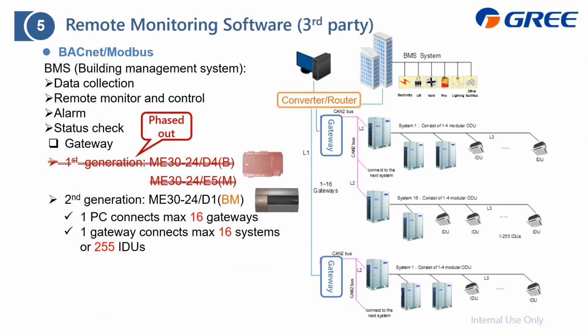We also allow to control or to monitor the VRF system from the PC. For this one, you just need a gateway acting as an adapter to handle the signal. This slide is the requirement for the third party, which means the software is not from our Gree. You can choose BACnet or Modbus. What you can do is collect the operating data and also monitor, check or control the VRF system. Also, you can set up your control logic to trigger the alarm or to check the status.